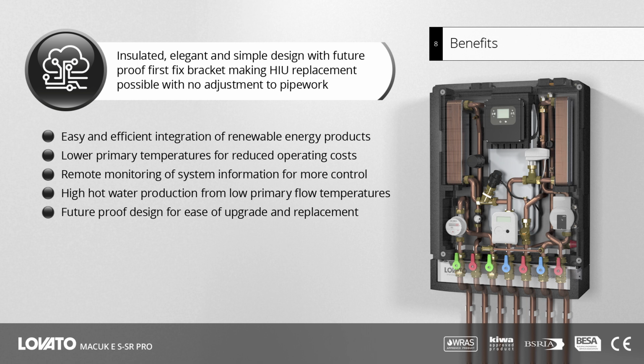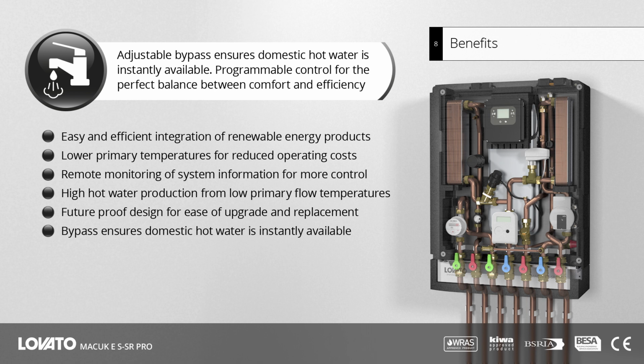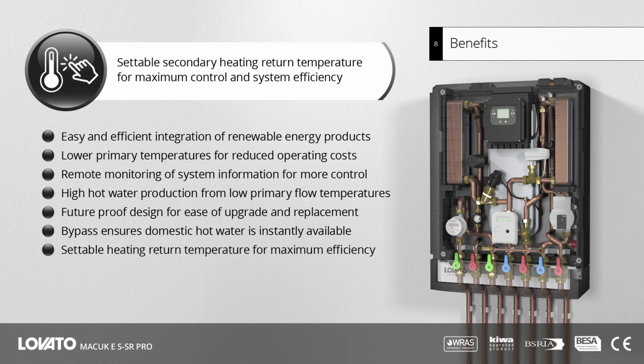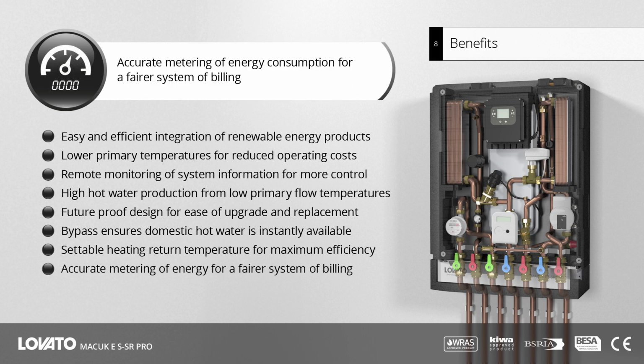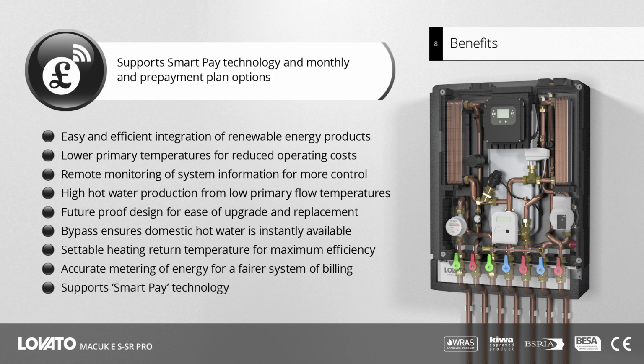Fully insulated, elegant and simple design with future-proof first fix bracket, making HIU replacement possible with no adjustment to pipework. Fully adjustable bypass, ensuring domestic hot water is instantly available and with programmable control strikes the perfect balance between comfort and efficiency. Fully settable secondary heating return temperature for maximum control and system efficiency. Accurate metering of energy consumption for a fairer system of billing. Support for smart pay technology and monthly and prepayment plan options.